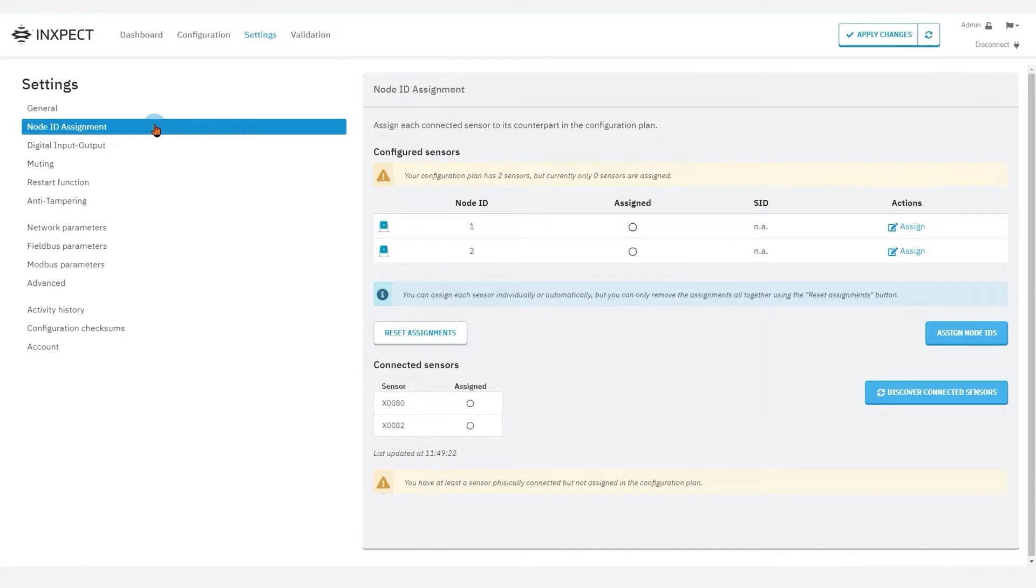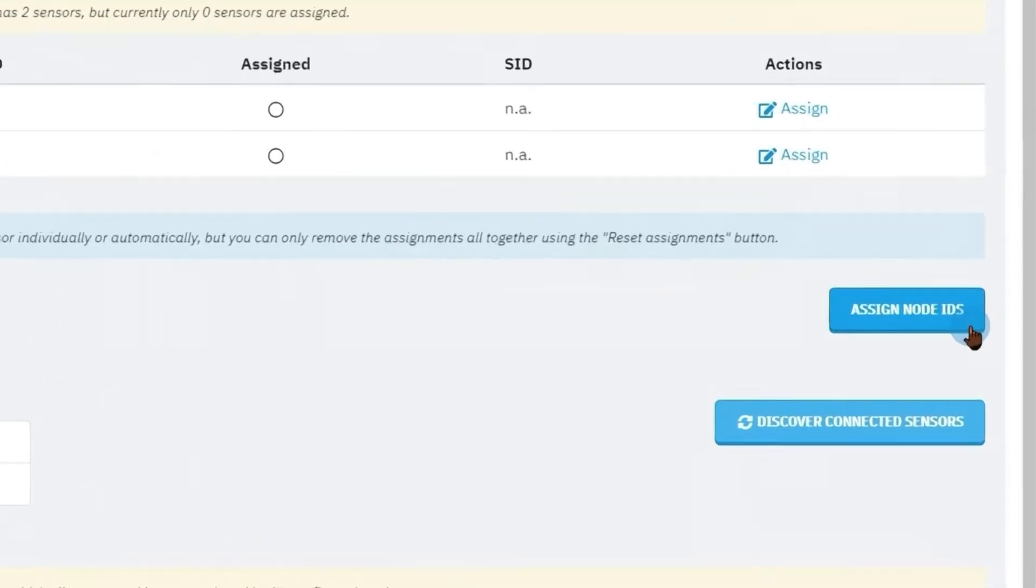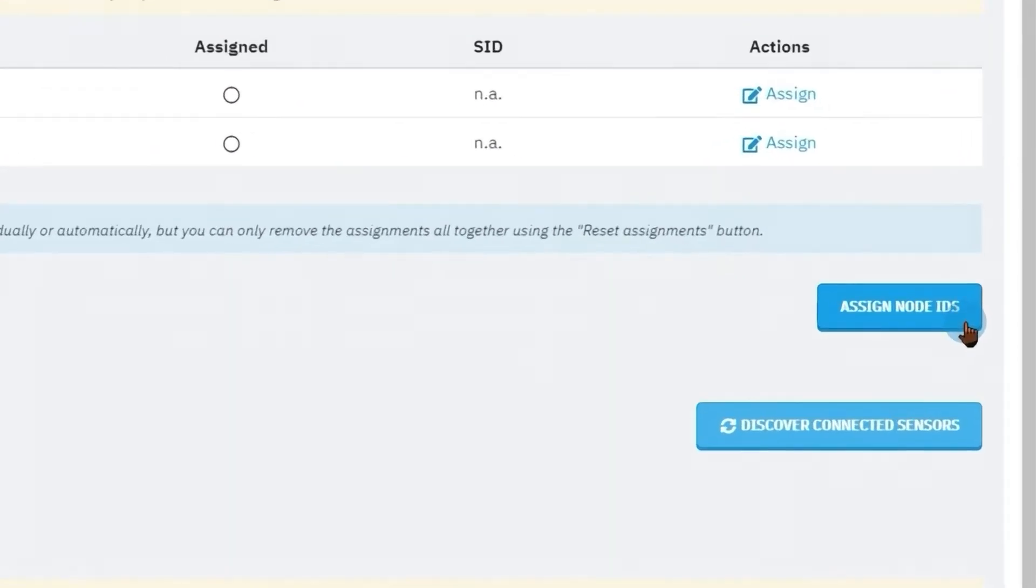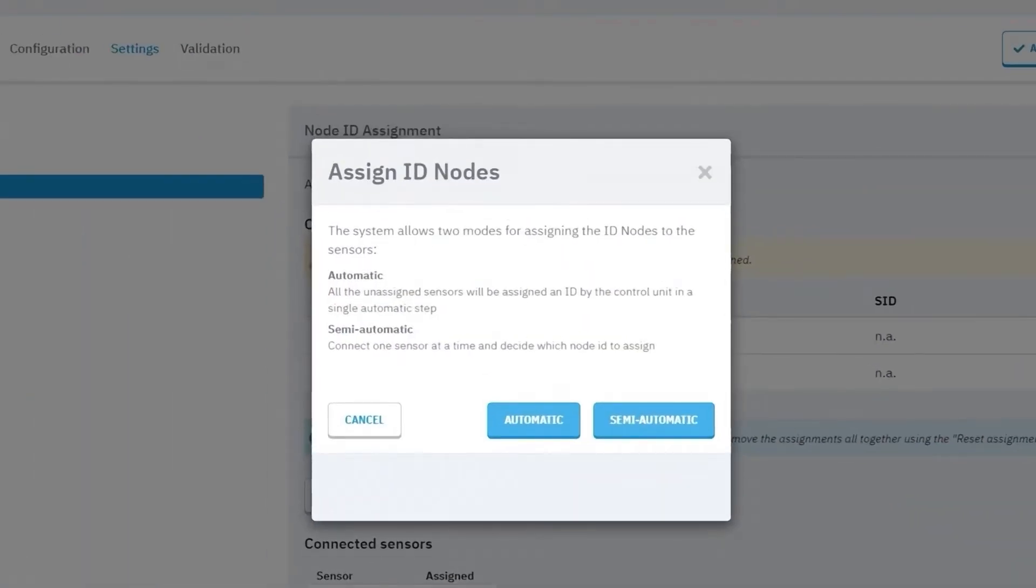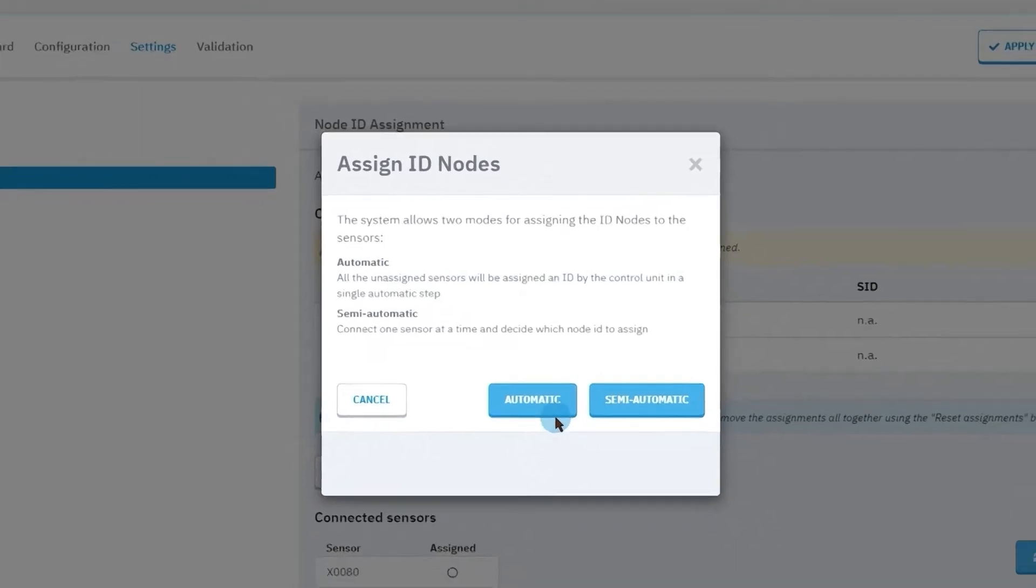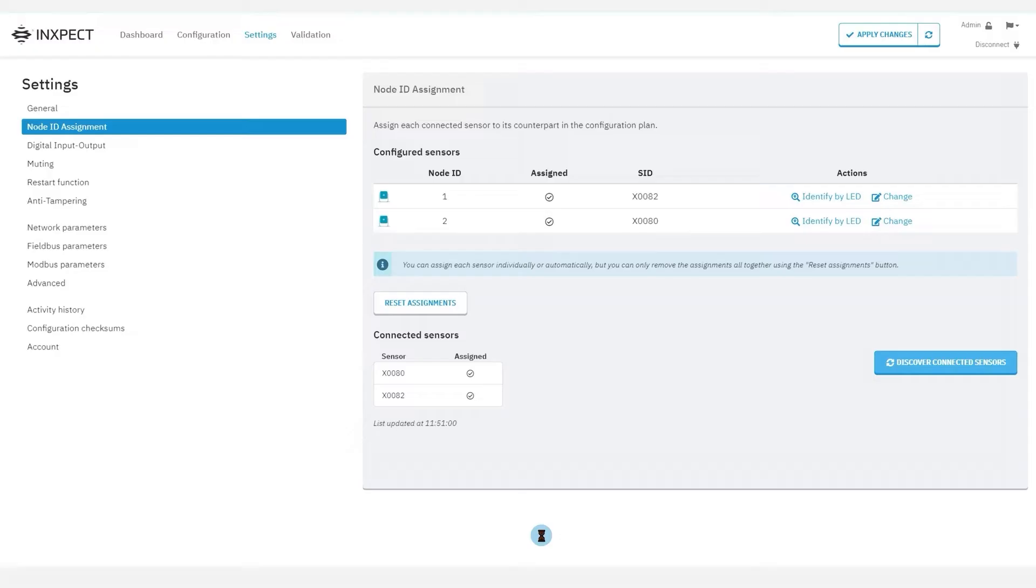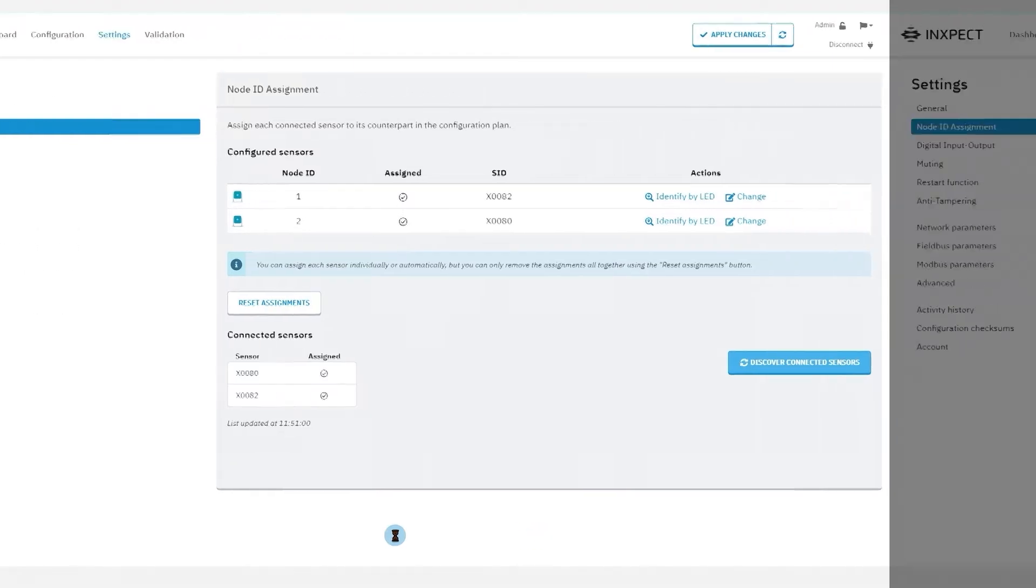Automatic, semi-automatic and manual. Let's start with the first two. When we click on the assign node IDs button, there are two different modes to choose from. Automatic or semi-automatic. In automatic mode, the node IDs are assigned to connected sensors in one shot, without following the order of the sensors along the chain.